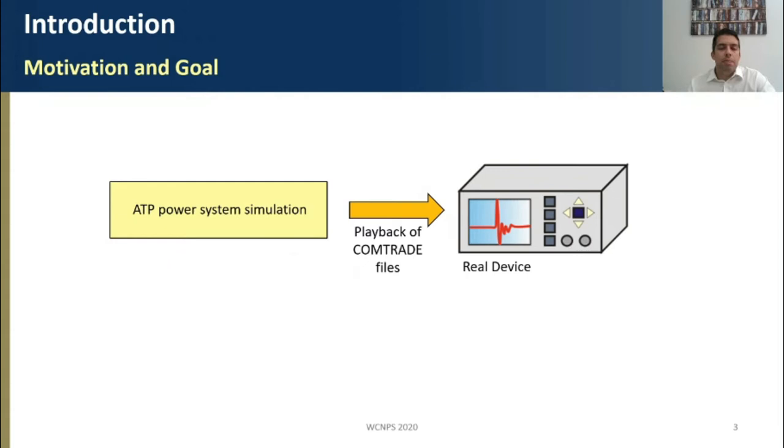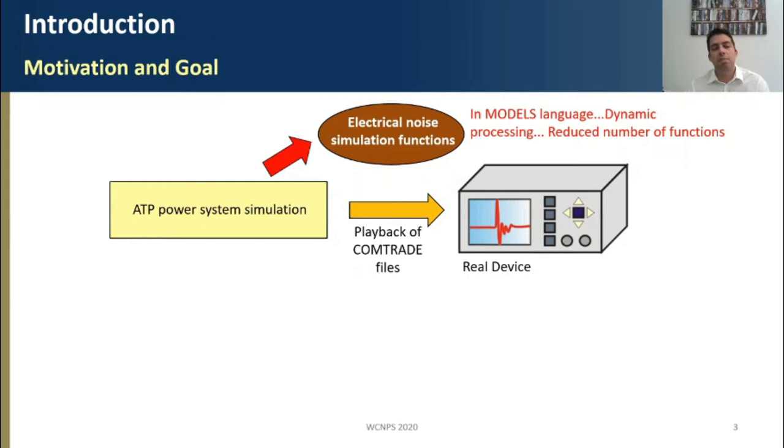When we do not have real-time simulators available, the ATP can be used to simulate power systems in order to test real devices. To do so, playback tests based on COMTRADE files generated by ATP are used. And looking towards the simulation of noise, we can think that the emulation of electrical noise directly in an ATP environment could be a good choice.